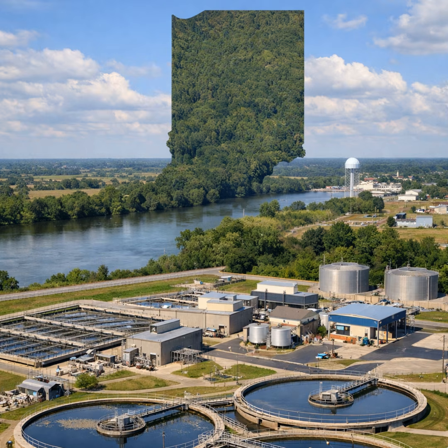So the mixed liquor volatile suspended solids are the amount of organic or volatile suspended solids in the mixed liquor of an aeration tank. The volatile portion is used as a measurement or indication of the microorganisms present. Volatile solids are organic or come from plants or animals. And then non-volatile solids are inorganic, such as grit, eggshells, and sand. So that's the difference between mixed liquor suspended solids and mixed liquor volatile suspended solids.